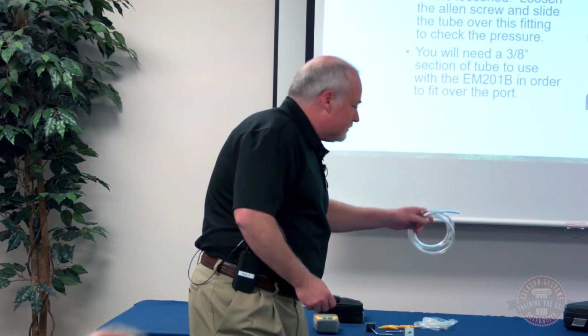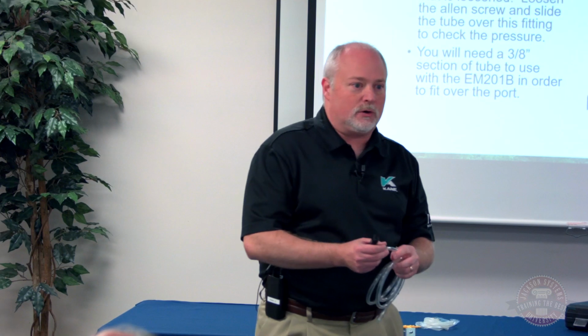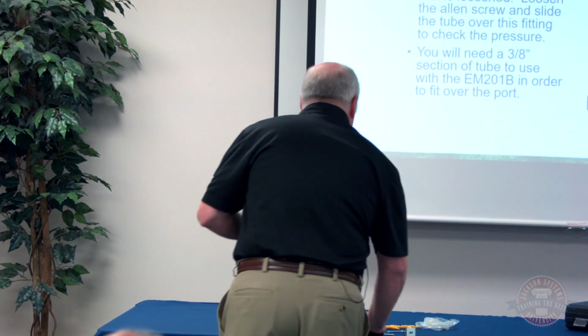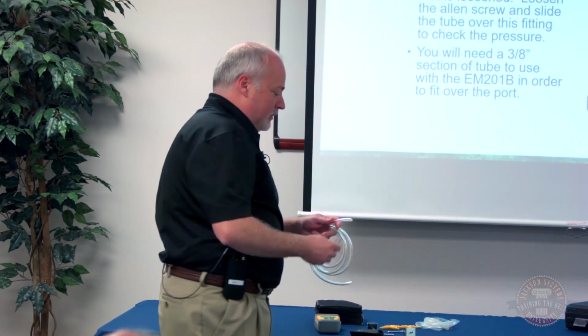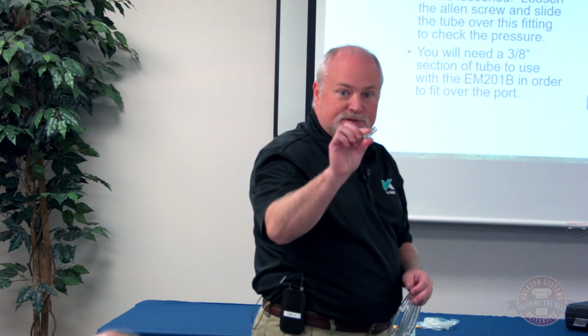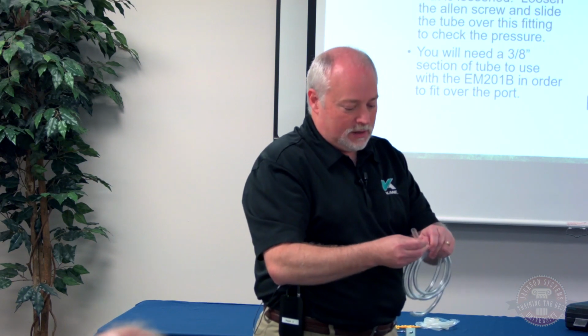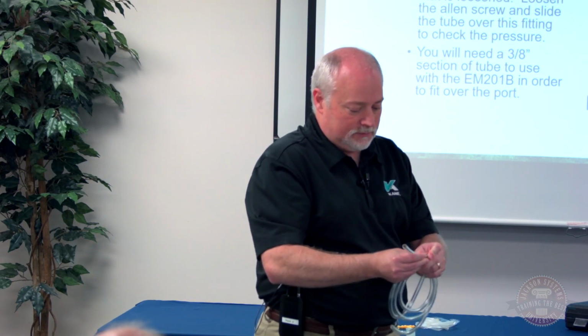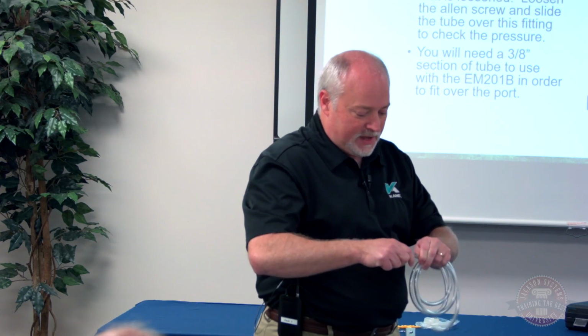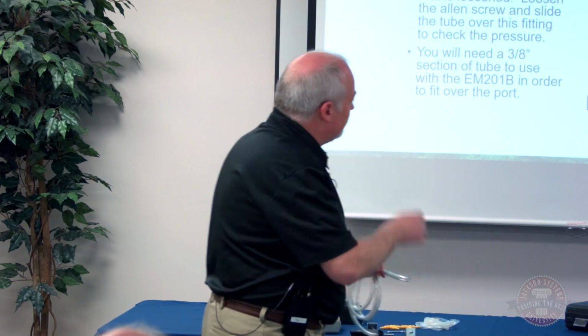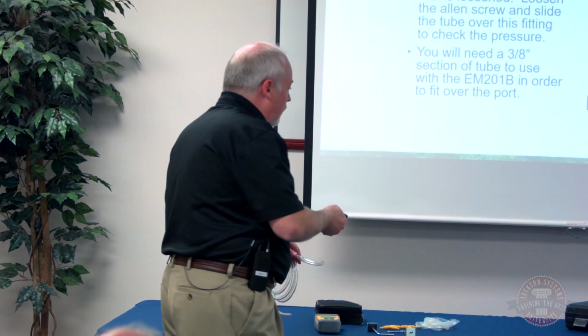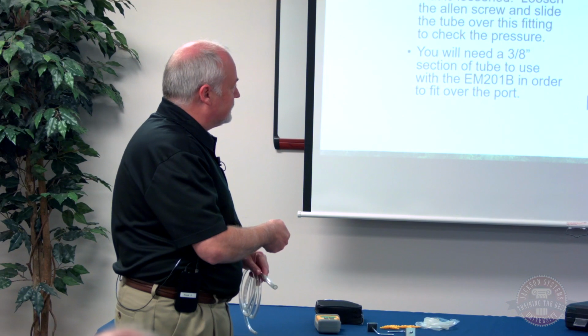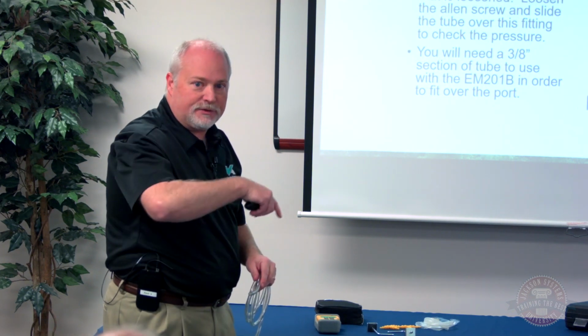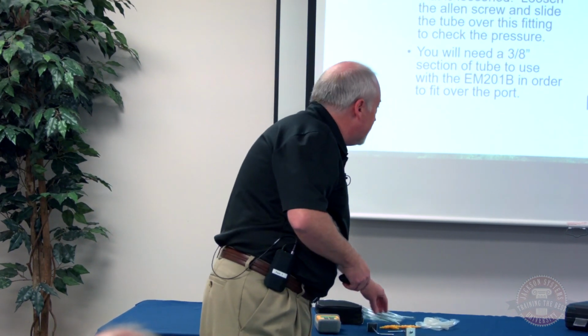Now the tubing that is included with the manometer generally isn't large enough to fit over that stub. I picked this trick up from one of our customers, a contractor, but this is just some 3/8 poly tubing, and if you're careful, you can slip that over the tubing that's included. Now that will fit over your pressure tap on this style of valve that just has the little spud that sticks up here, rather than the plug that you're going to remove to check your gas pressure.